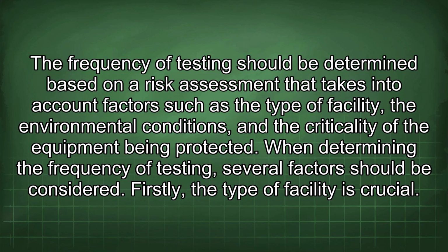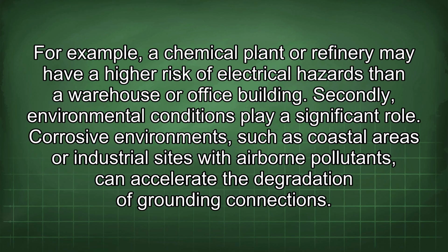The frequency of testing should be determined based on a risk assessment that takes into account factors such as the type of facility, the environmental conditions, and the criticality of the equipment being protected. When determining the frequency of testing, several factors should be considered. Firstly, the type of facility is crucial. For example, a chemical plant or refinery may have a higher risk of electrical hazards than a warehouse or office building.